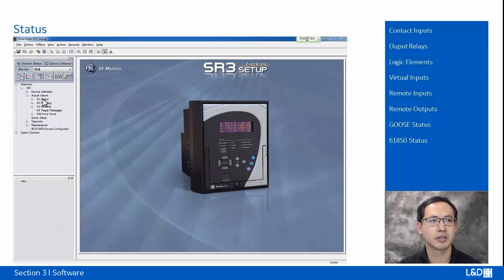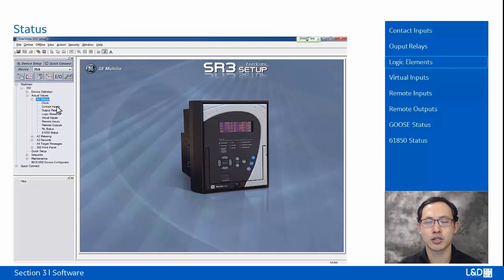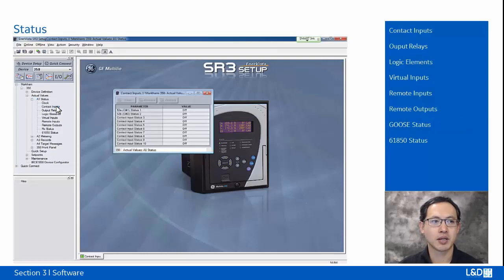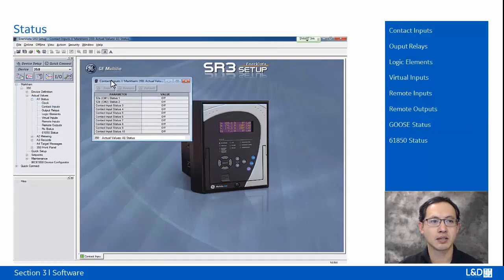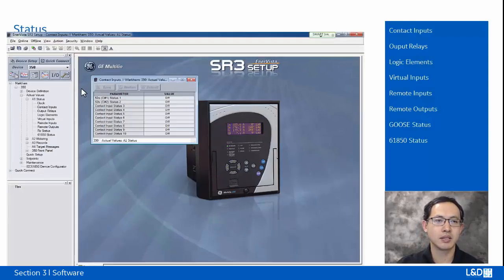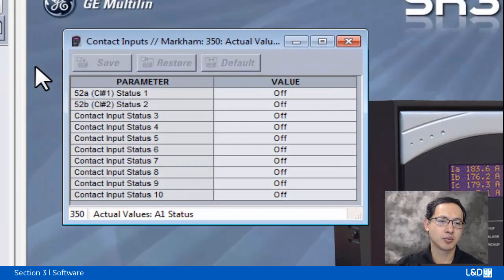Just double click Status A1 and we can check the status for the clock, contact inputs, output relays, logic elements, virtual inputs, remote inputs outputs, GOOSE status, and 61850 status. So here is one example for the contact inputs. We can double click contact inputs and use a pre-wired test set to apply the DC to the contact inputs 1 to 4 by turning on the switch 1, 2, 3, 4.